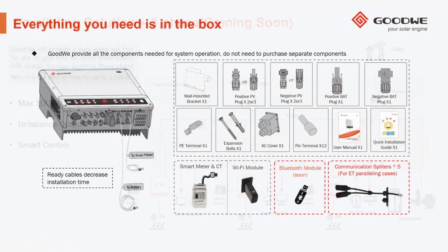With our hybrid inverters, everything you need is in the box. There are no extra components required to install a system. There are some extra components which we are bringing, like the parallel box or the LAN module for the inverters, but those are all optional extras that aren't required to install a system. With our 3-phase ET paralleling systems and the communication device, we'll also include the connection splitter, so that you don't have to make up any cables and you still have your IP rating of the inverter. We also quite soon are going to be releasing our Bluetooth module, which will allow direct app commissioning even when your inverter is connected to the network.